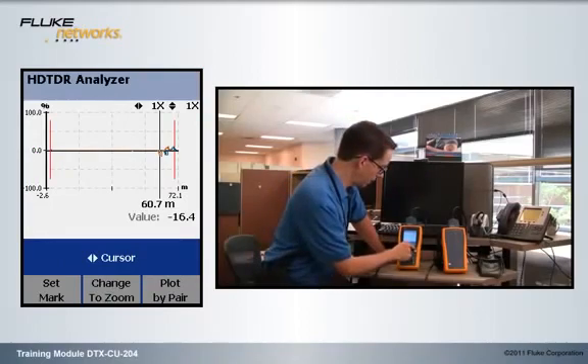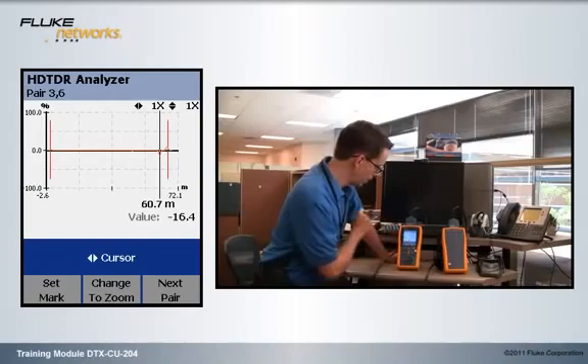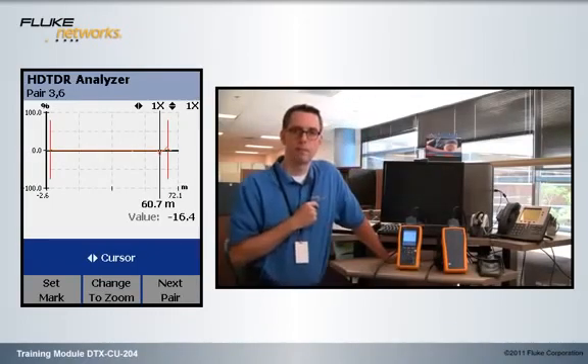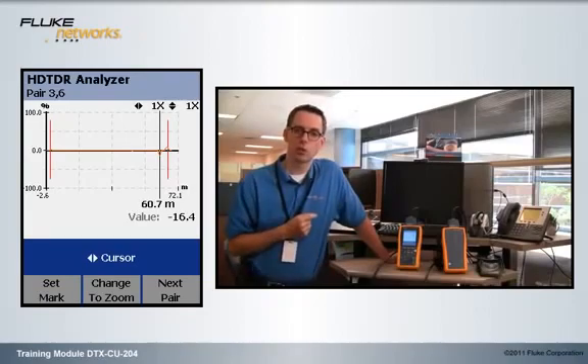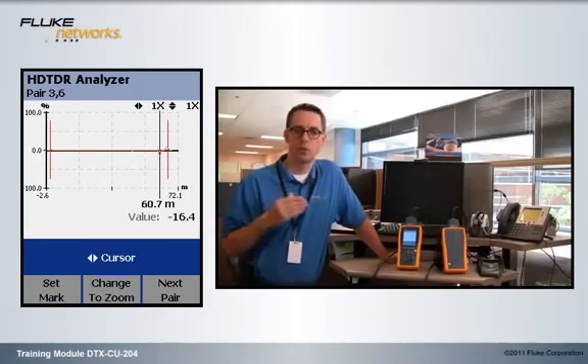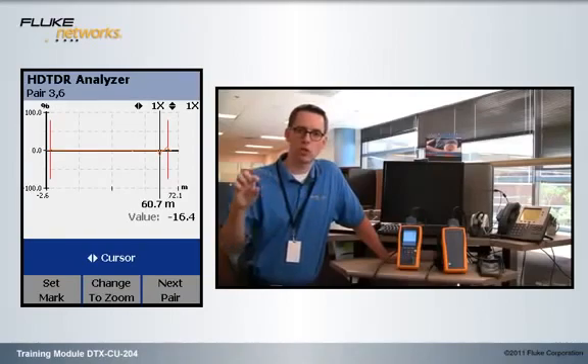Then I'm going to hit the F3 key. And I'm going to hit it until I get to pair 36. I'm only doing that because that's the shortest pair. That'll give me the correct distance to the fault. Because when you're talking about measuring the outer sheath, that's done based on the shortest pair in the cable.